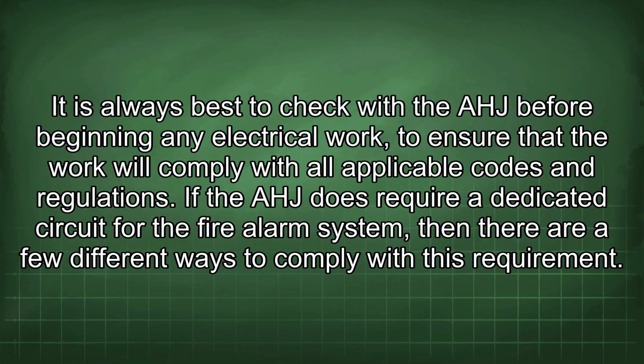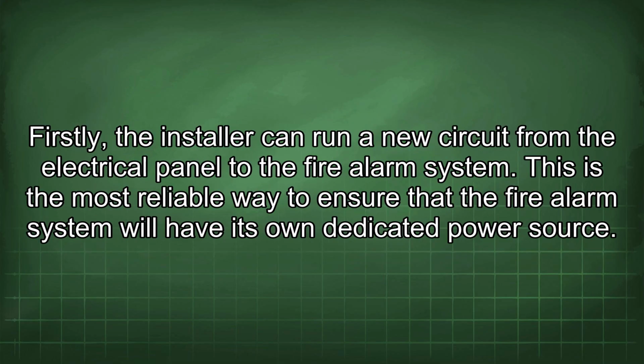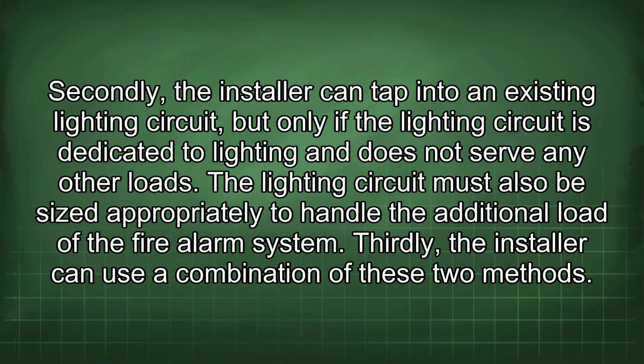If the AHJ does require a dedicated circuit for the fire alarm system, then there are a few different ways to comply with this requirement. Firstly, the installer can run a new circuit from the electrical panel to the fire alarm system. This is the most reliable way to ensure that the fire alarm system will have its own dedicated power source. Secondly, the installer can tap into an existing lighting circuit, but only if the lighting circuit is dedicated to lighting and does not serve any other loads. The lighting circuit must also be sized appropriately to handle the additional load of the fire alarm system.